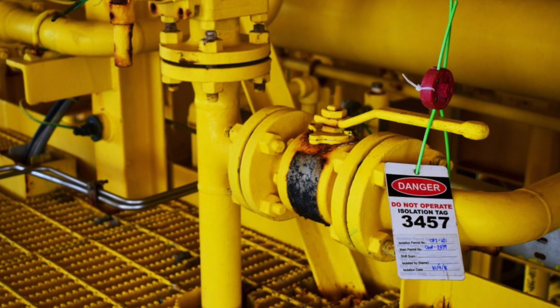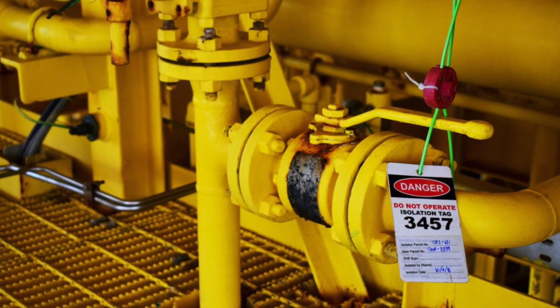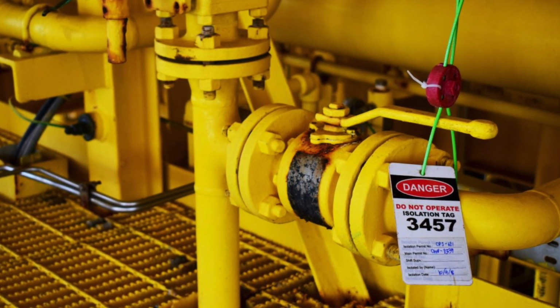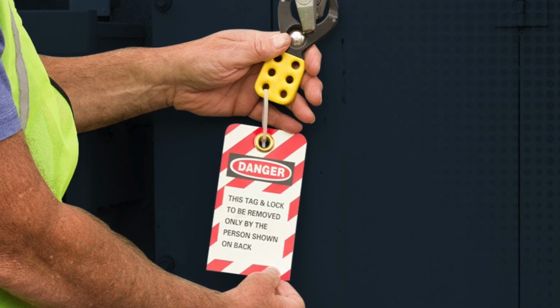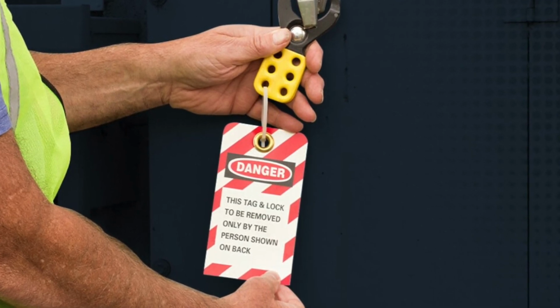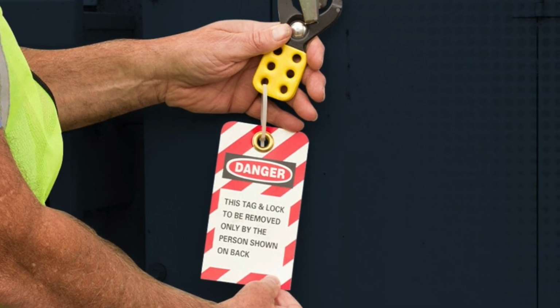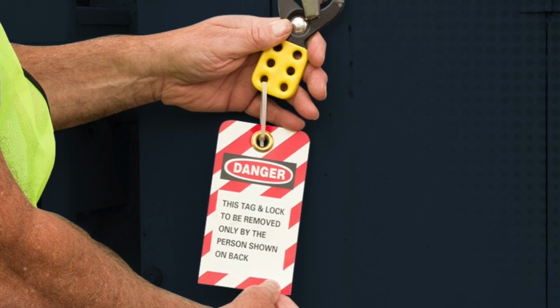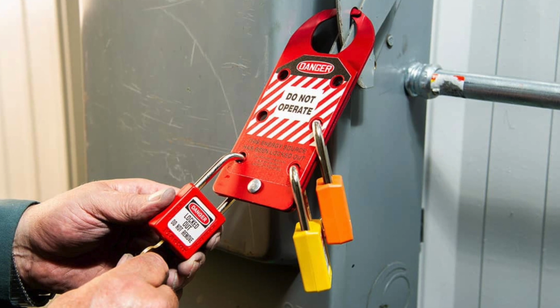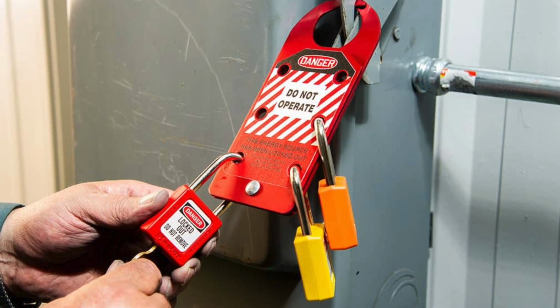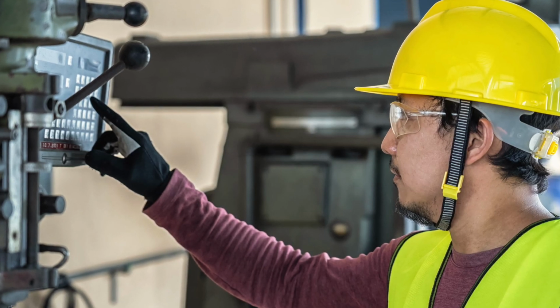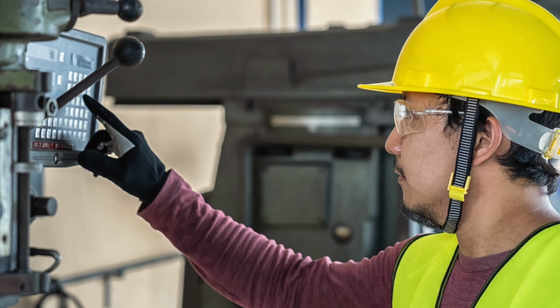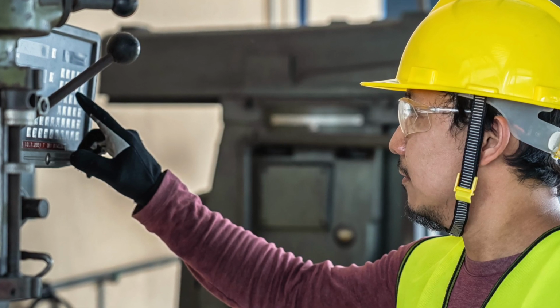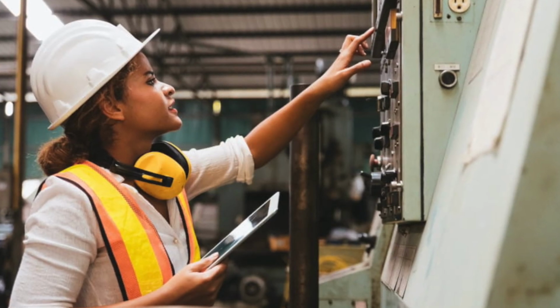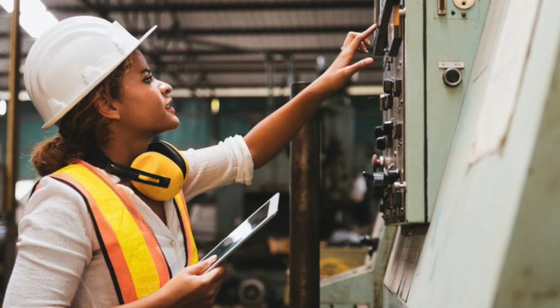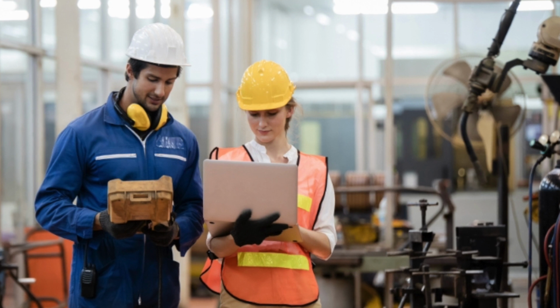Other special situations arise when multiple pieces of equipment are powered by the same energy sources, or when the piece of equipment you are working on is linked to other equipment. Here, supervisors should be contacted before any lockout tagout work is performed. Another special situation occurs when a system must stay on while it is being serviced because the functioning of the equipment is essential to the facility's normal operation. Again, you need to consult your supervisor.